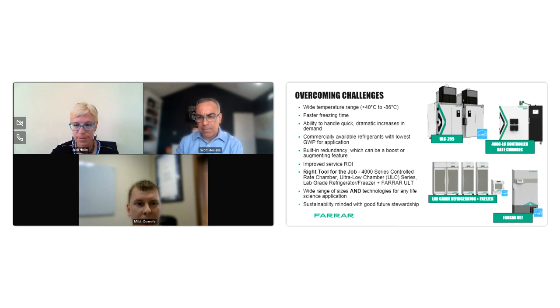It only runs one temperature at a time, but you could qualify it for any temperature required for your process. We have a controlled rate chamber that helps freeze and thaw product, which can be used in a processing or manufacturing environment, bringing product down to temperature quickly or rapidly, or controlling the flow of freezing so that it steps at a certain rate based on whatever the process requires for that particular drug substance.